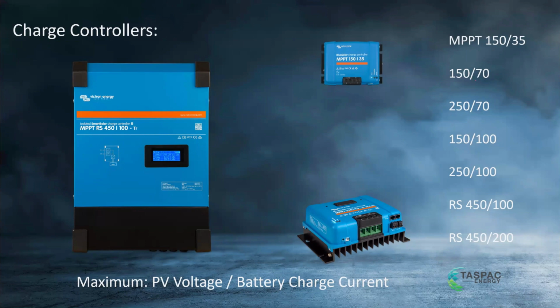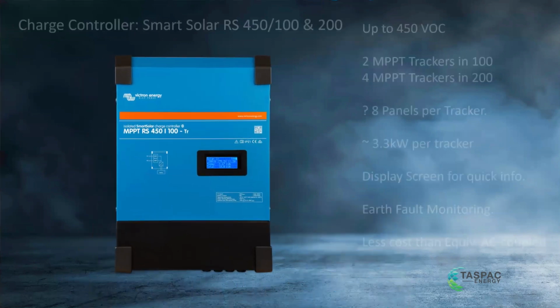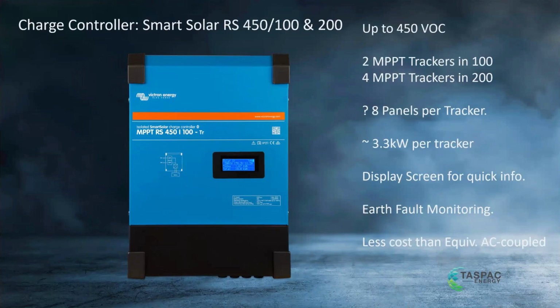And so we carry the 150/70 and the 250/70, so you should know that means 250 volts input on the solar side, 70 amp charging. We carry the 150/100, the 250/100, and we carry the new models as well, which are the bigger one on the left there, the RS 450/100, and its big brother, the RS 450/200. So let's have a quick look at those units there. The RS 450 means you can go up to 450 volts open circuit, which you're going, oh yeah, so what?